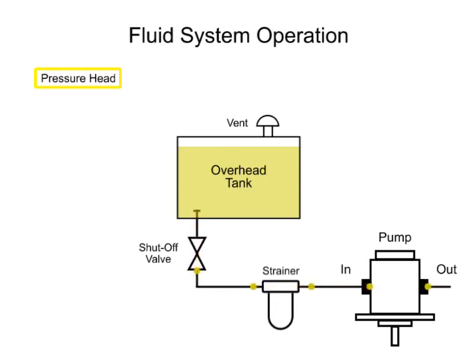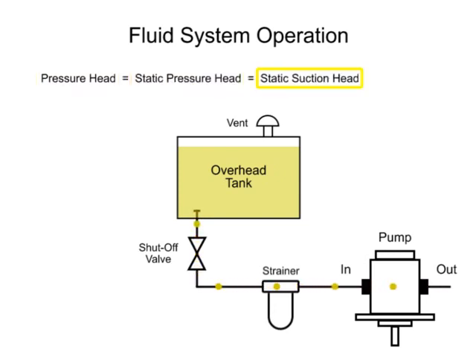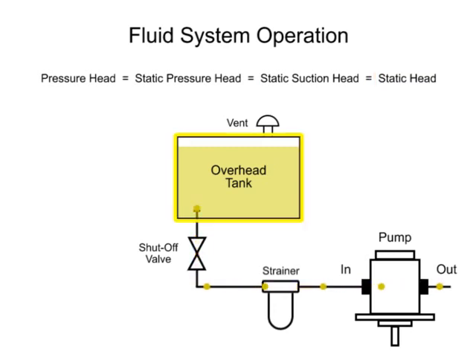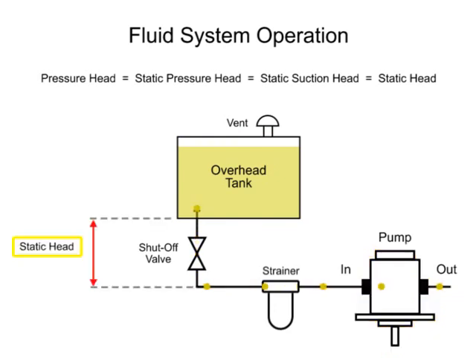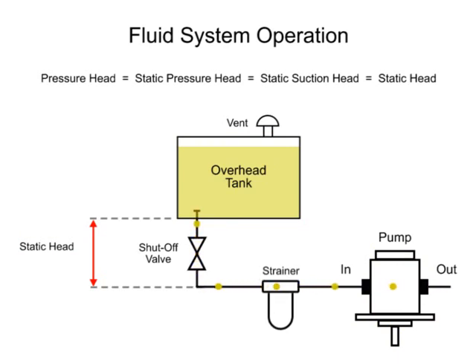Pressure head, also called static pressure head, static suction head, or static head, is created when the reservoir is placed at a height higher than the centerline of the pump, and is the measure of distance from the pump to the tank. This creates a positive inlet pressure and helps fluid flow to the pump.